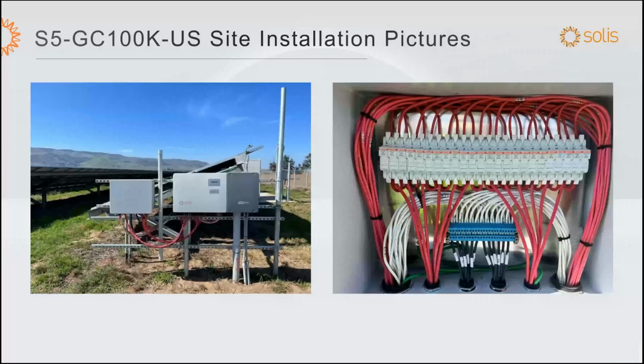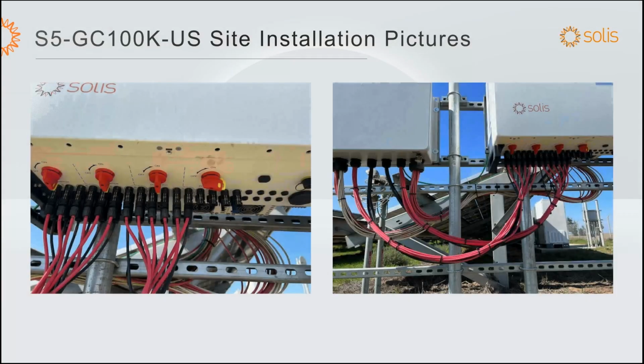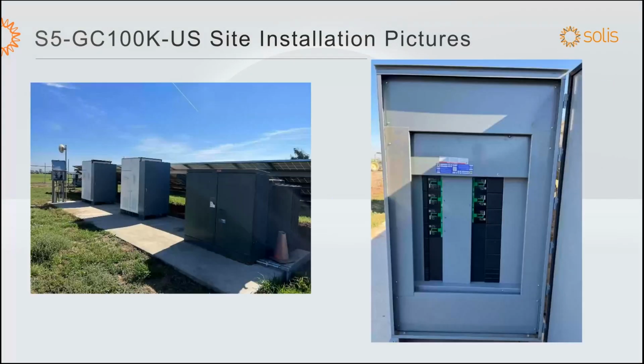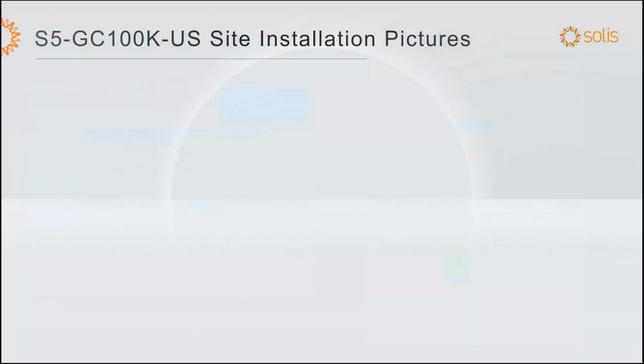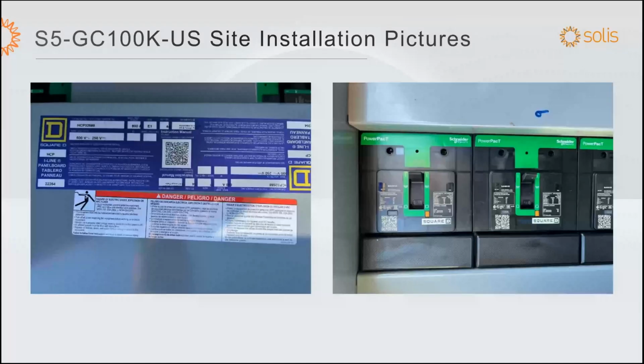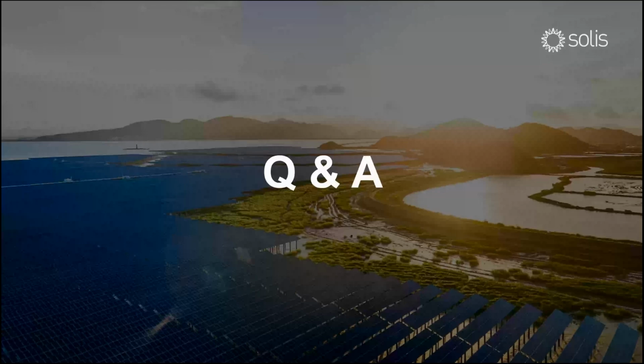Also here I would like to show an example of a repowering project that was done, combining, in this case, an external combiner, but it could be done with a Y connector the same way as shown before. In the presentation, we added switchgear that connects those inverters to the medium voltage transformer, along with the rating of the switchgear, and now we'll go to the Q&A session on this presentation.